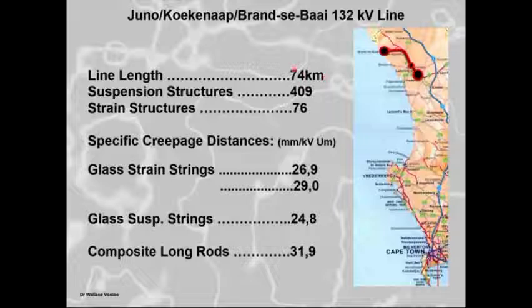You find that on the 74 kilometers, we've got suspension structures, 409 of them, and we've got strain structures. Now, we obviously know with the suspension structures the insulator is in a vertical position and the conductor is hanging from it. And with the strain structures, the insulator is horizontal and the conductor is actually pulling the insulator. And so it's putting strain on the insulator. The conductor is not being suspended by the insulator. So we've got 409 suspension structures and we've got 76 strain structures.